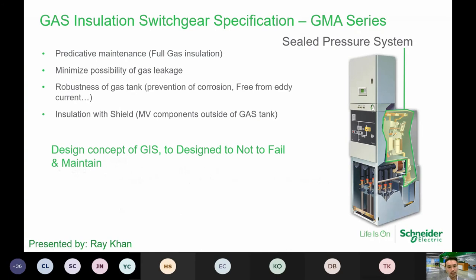The SF6 gas is housed in a compartment that is fully sealed, or what they call hermetically sealed. This sealing is tested in the factory, so in a way this gives users predictive maintenance. By having it fully sealed, it minimizes the possibility of gas leakage unless the tank has been damaged by users. Otherwise, the possibility of leakage is very, very low. Because of the robustness of the tank and the metal shielding, it also prevents corrosion, and you have the insulation with shielding within the tank as well.